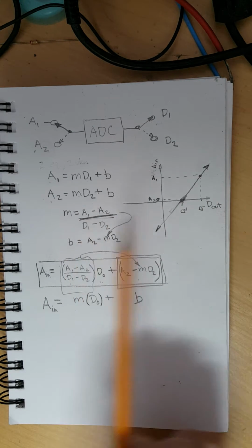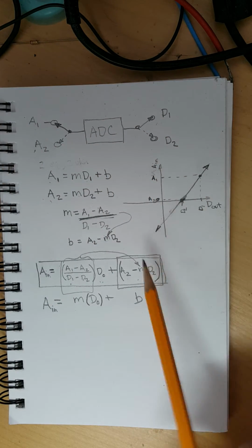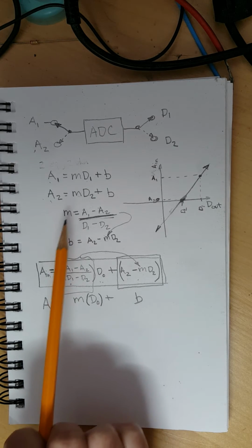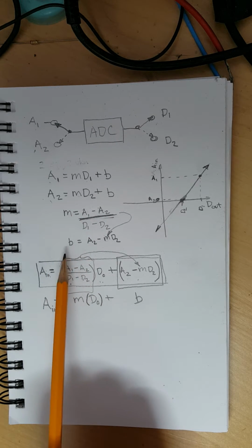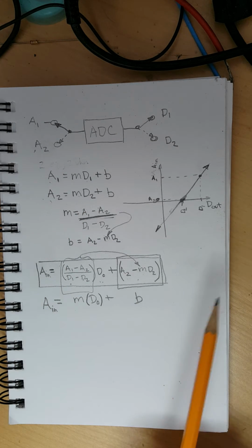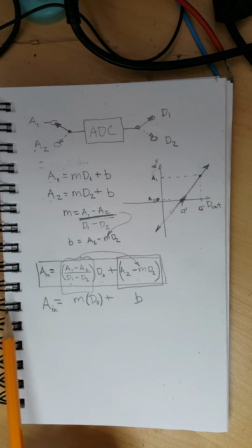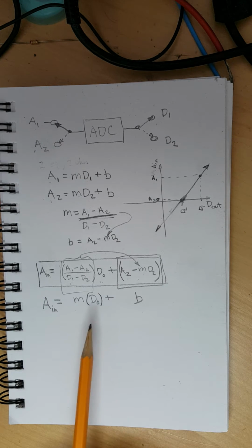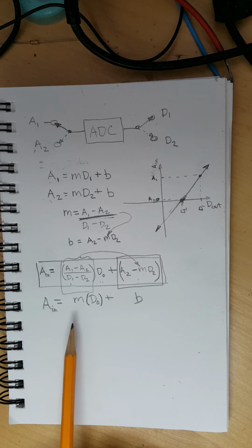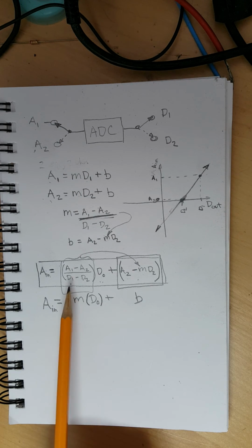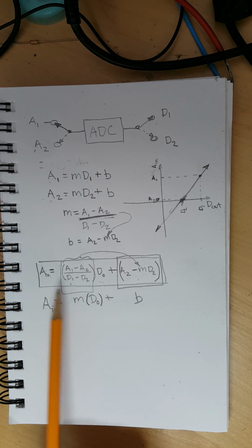These D and A values correspond to points on a line, which was the function we want to line it up with. So from that, we can get the slope, rise over run. And then we can also compute B, and we get an overall equation that translates the output to the input, so we get the correct analog input based on the digital reading. By the way, we're measuring these values, so we want the actual value at the input. So basically we come up with a function of A-in equals the slope, which in this case would be A1 minus A2 over D1 minus D2.